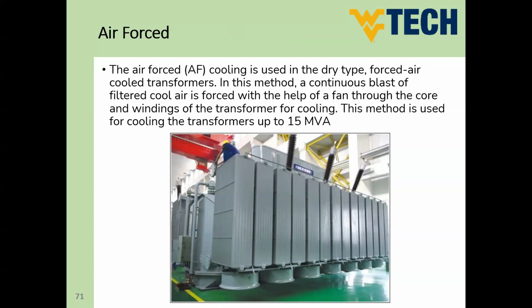This is air forced. So for the air forced, guys, used in the dry type forced air cooling transformers, in this method, a continuous blast of filtered cooled air is forced with the help of a fan through the core and windings. So you have tubes for this air, or like radiators for this air, moving with forced air to cool the winding and core. This method is used for cooling the transformer up to 15 megavolt ampere. So up to 15 megavolt ampere, it's good to use air forced. And here, as you can see, these are the bushings of the medium voltage side. Okay. This is 15 megavolt ampere.